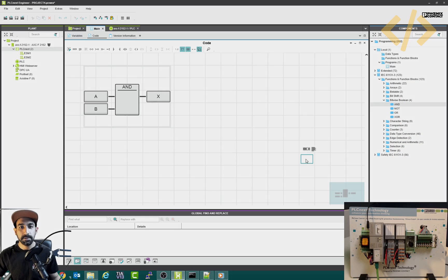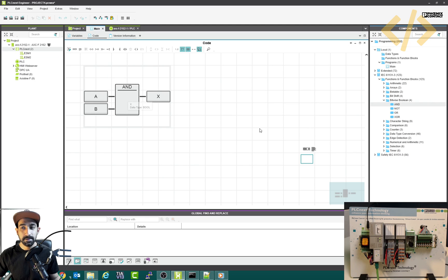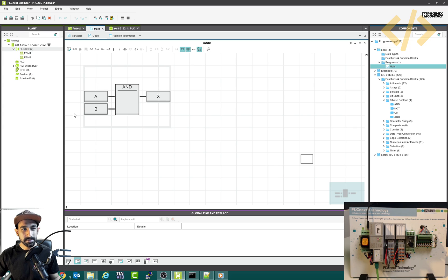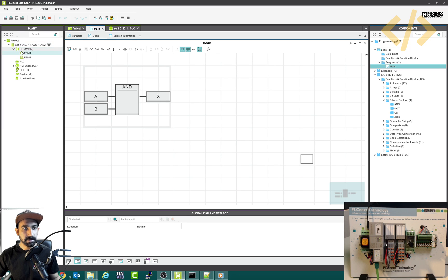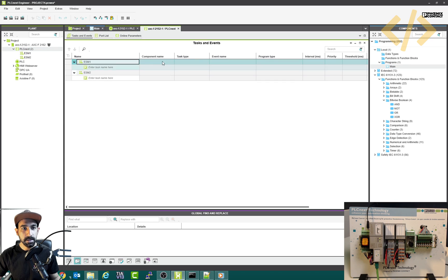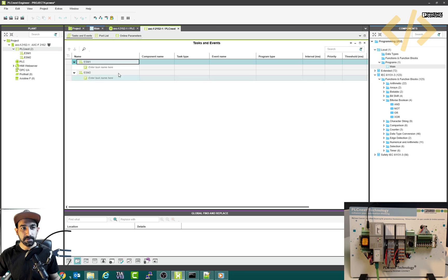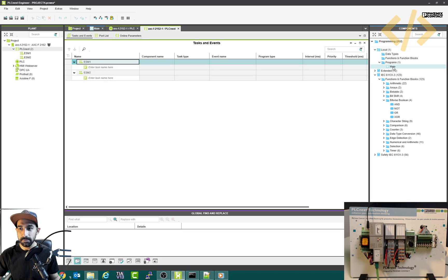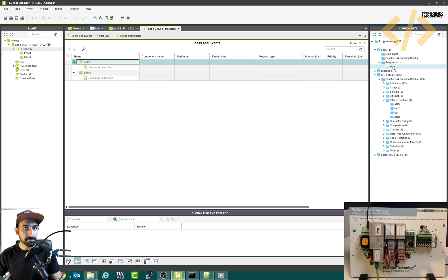Alright, now the PLC program is defined here. So this is in the main program. Now we have to put this program in the task. Because in this PLC, you can see here if you click this PLCnext, if you open this one, we have some tasks and events. So we have to define the task in this ESM one. And the task is our main program. Otherwise, this will not be executed, we have to define it in the PLC.